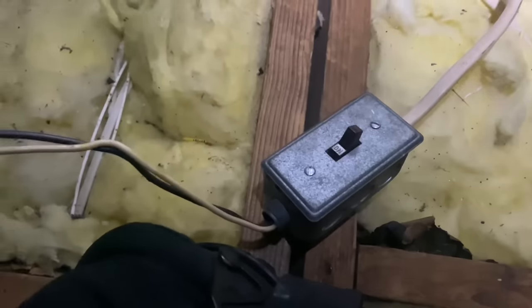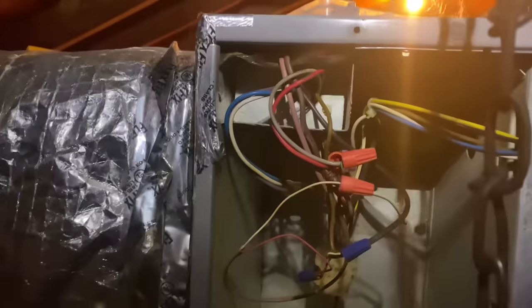Let's go. All right. So we're just disconnecting everything you could see. This is where my raw electric was going through. I have the circuit breaker panel off. I used my non-contact electrical tester by Fluke. There that is. And we have no power there, right? Because it's off at the breaker. We're gonna put this off to the side right now. And I did put some Wagos on there, the Wago two conductor, the 221 model. Just put that off to the side there, out of the way. Right, and I'm gonna start disconnecting the thermostat condenser wire, which is gonna get replaced anyway. And overall, pretty clean in here. So let's get rocking and rolling here.